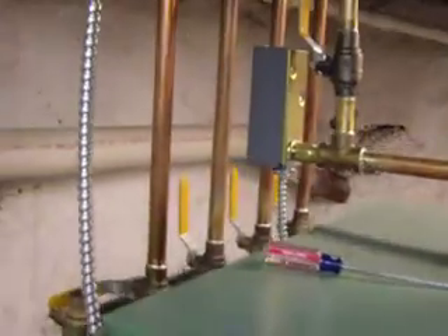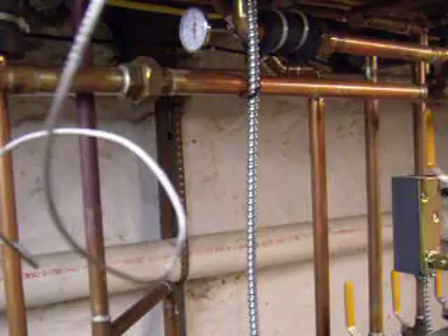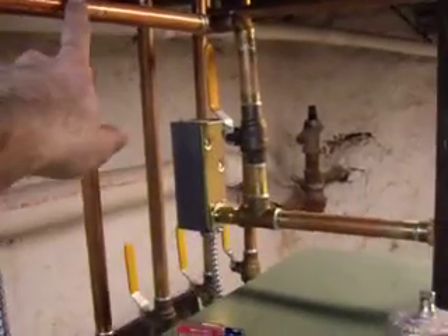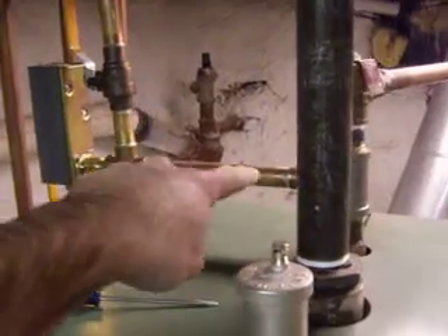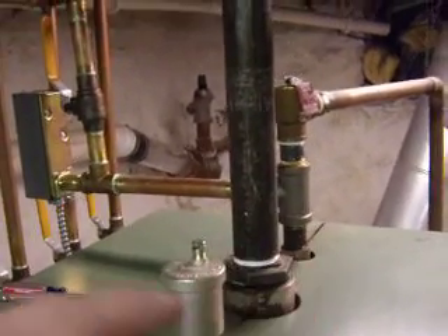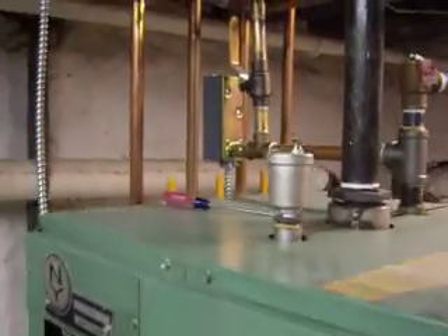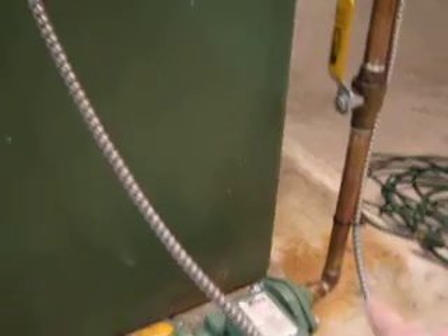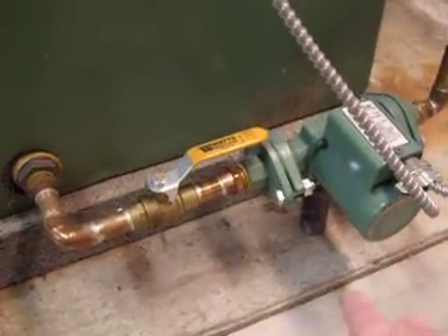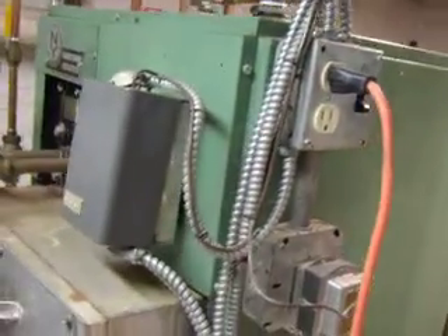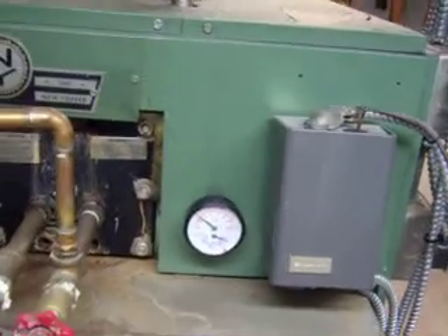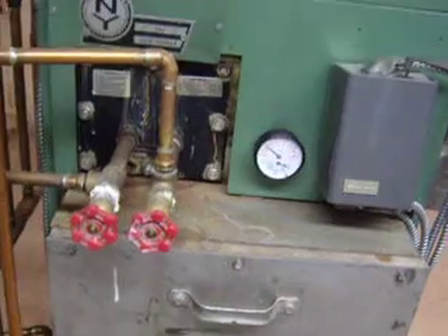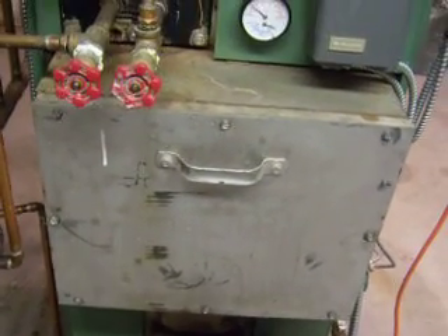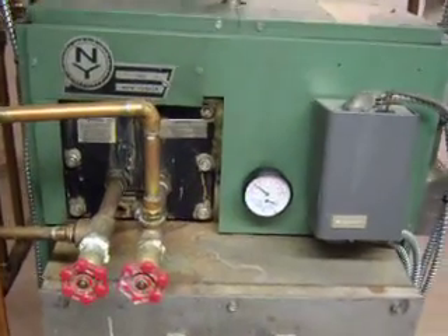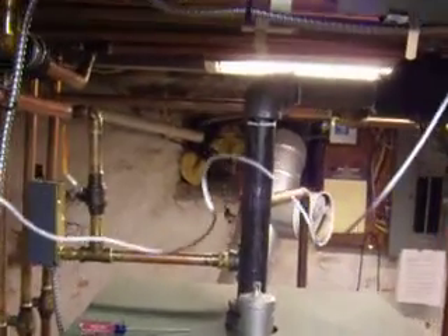And then what I have is a secondary loop. I know this is difficult to see. I have a secondary loop coming in on a separate circulator pump. So what it's doing is it's bringing the hot water into the bottom of the boiler through another circulator that's on a separate aquastat, and it keeps the entire boiler up to temperature. As long as the oil boiler stays over 135 degrees, it does not kick on. If the wood fire outside drops for any reason, the temperature drops, it will automatically kick the oil boiler back on to recover the heat in the house.